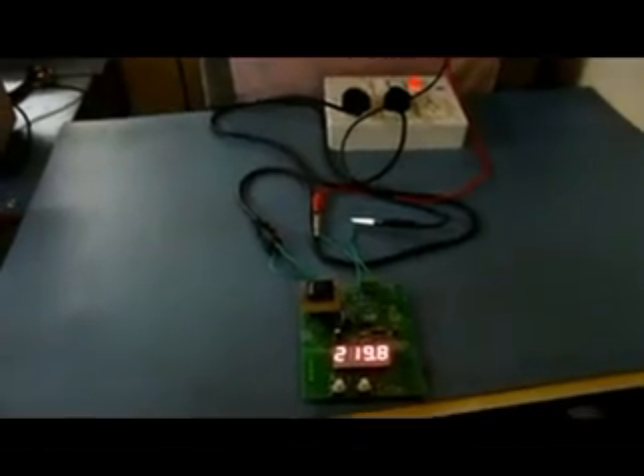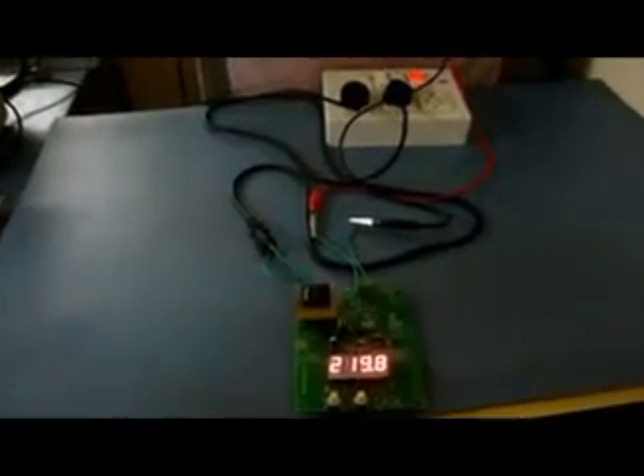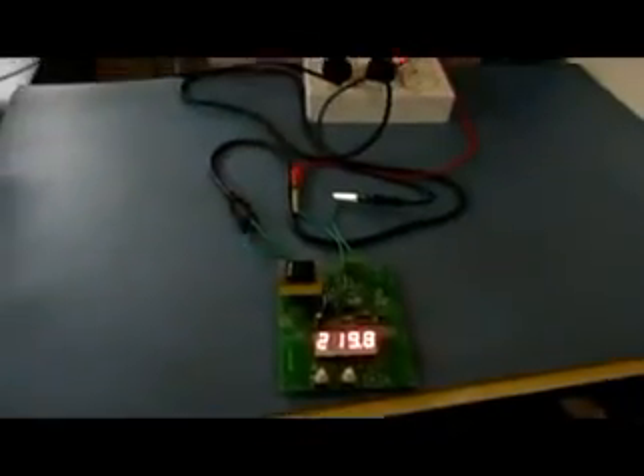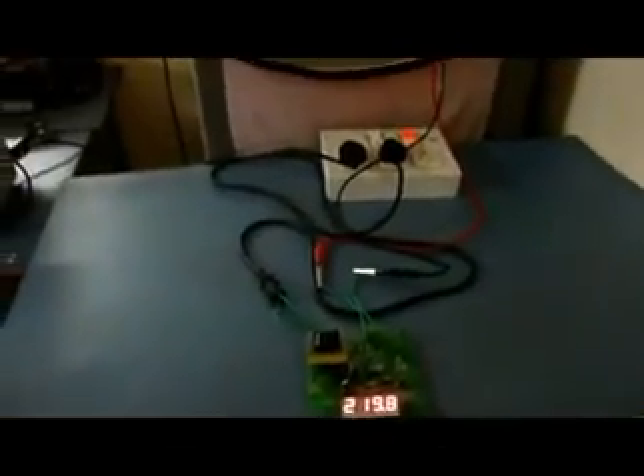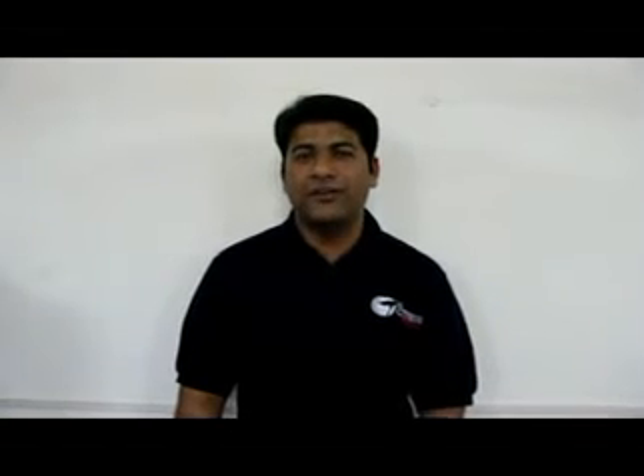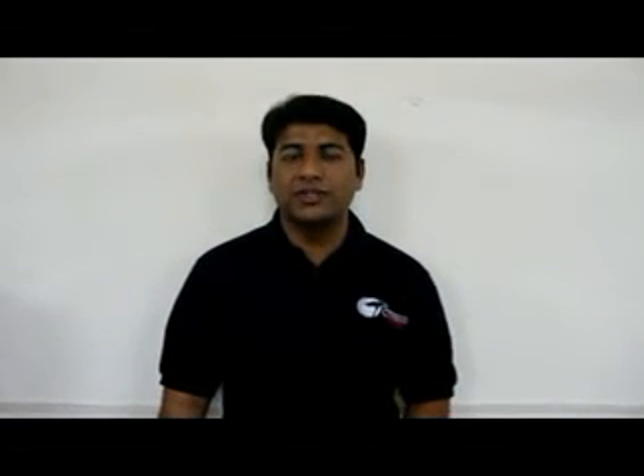We are reading 219.8. The frequency meter shows 61.99, and the voltage reads 219.8. So we have perfectly matching readings throughout the range. So we have seen the demo of the performance of the DPM by changing the voltage, by changing the frequency. So I would like to emphasize that the solution here by Cypress is a programmable solution, a very cost-effective solution to address the needs of the digital panel meter market.